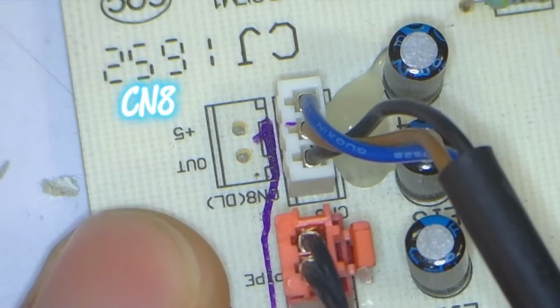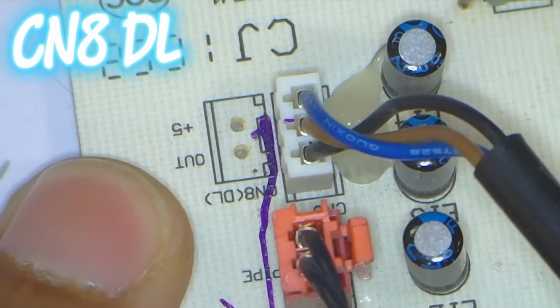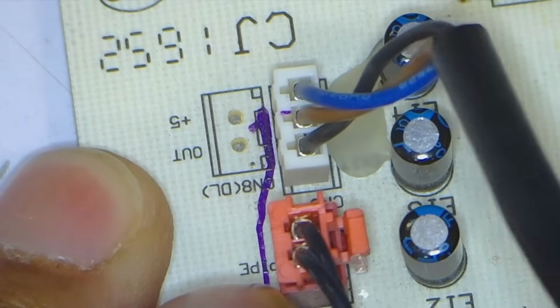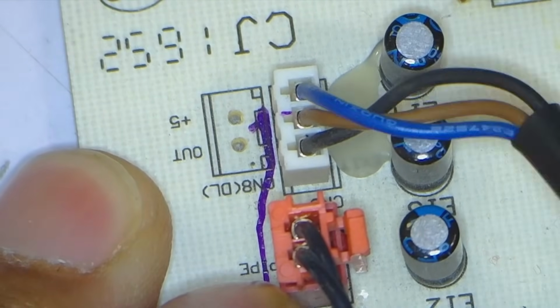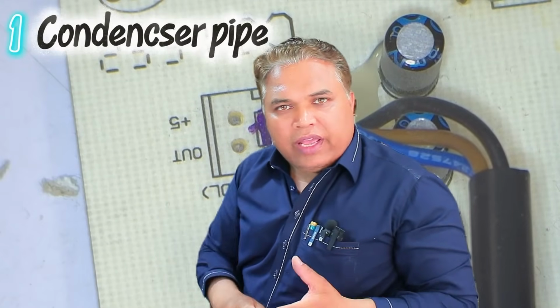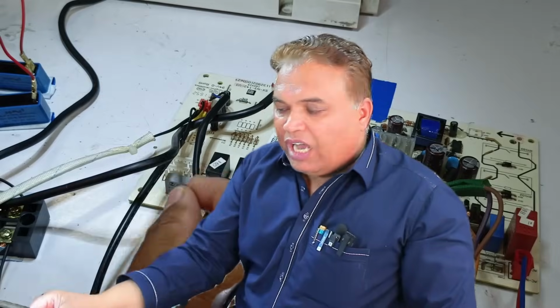An additional feature in this system is that the outdoor sensors are also connected to the indoor PCB, not to the outdoor board. You can see here the connector labeled CN8DL, and the three wires connected to it are used for these sensors. This system includes two sensors. One is installed on the condenser pipe, and the other is placed on the discharge pipe. The third wire is for the low-pressure switch. All three of these functions are controlled by the indoor unit.